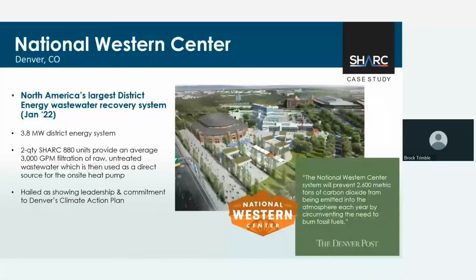And finally, the largest project to date, which was just commissioned about 6 months ago in Denver, Colorado, the National Western Center. This is North America's largest district energy wastewater energy recovery system to date. This is a 3.8 megawatt district energy system, moving energy to and from the sanitary sewer in order to gain access to energy for heating or reject energy for cooling. This unit sees two of our SHARC 880 units, providing roughly 3,000 gallons a minute of wastewater filtration, using that as the heat source and heat sink. And what they anticipate is that year over year, this project will prevent roughly 2,600 metric tons of CO2e per year from being ejected into the environment.